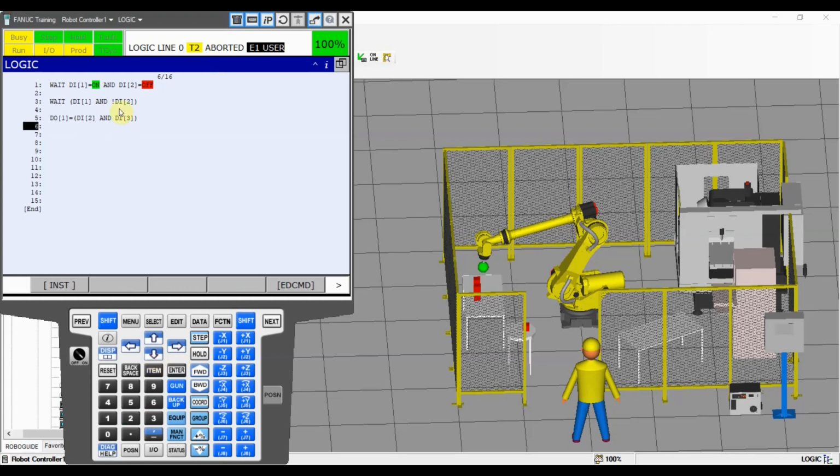So this is again a kind of mixed logic in here, and in a normal statement, this would be like digital output equals to on when this and this are on. And that's exactly what the mixed logic is doing. So this output will turn on if digital output 2 is on and digital output 3 is on. So we used a mixed logic with the digital output statement. And you can program the same for flags, registers, and so on. Again, we'll talk about it in the next video.